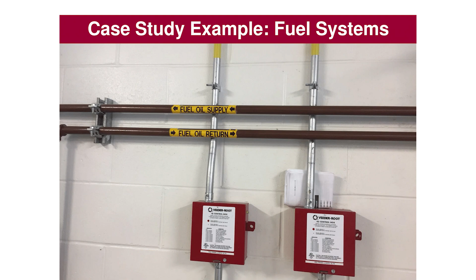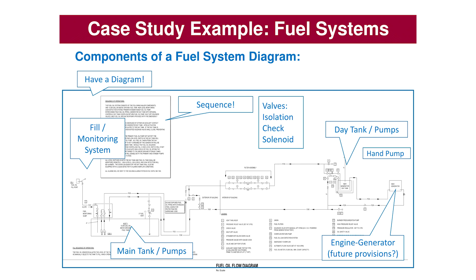One of the things we want to look for is that there's actually a fuel system diagram of some sort in the construction documents. Where we're doing a design review, that's one of the first places I'll look, because one of the most important things is to have a fuel system diagram that lays out all the different pieces, parts, and components of the system - that there's an actual sequence of operations. What happens when the generator starts? When are the day tank pumps and main pumps supposed to turn on? When are they supposed to turn off? Has anybody really thought that through?